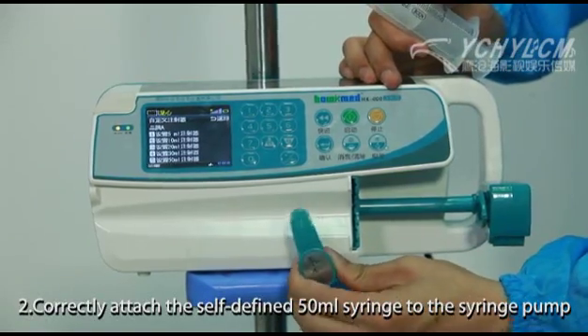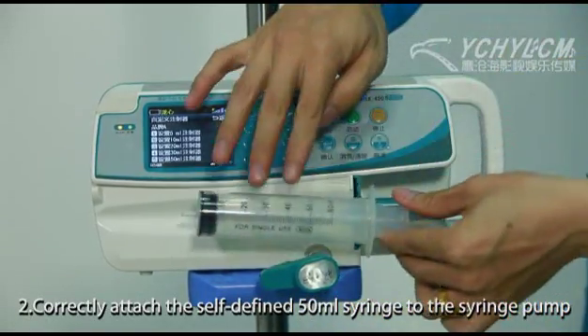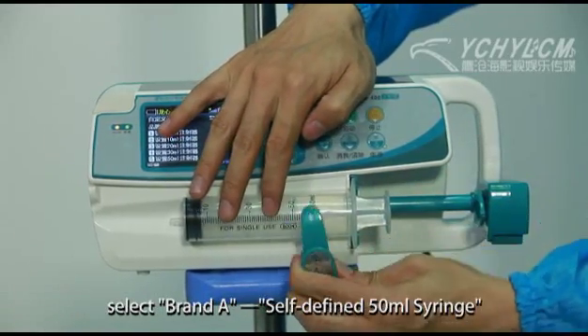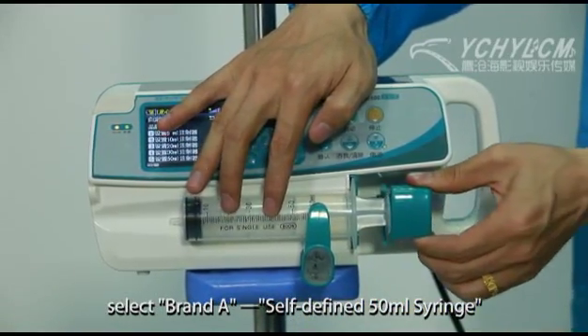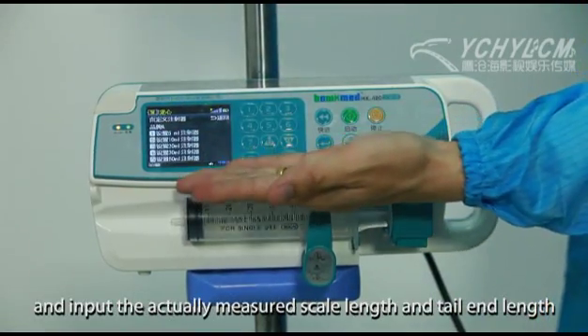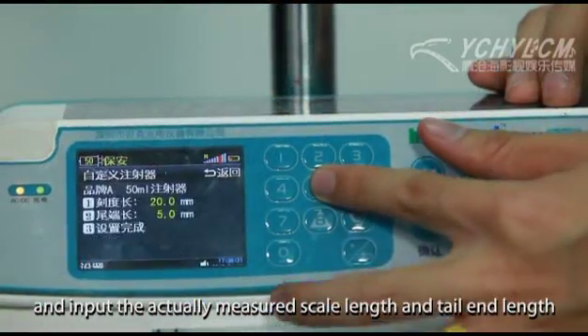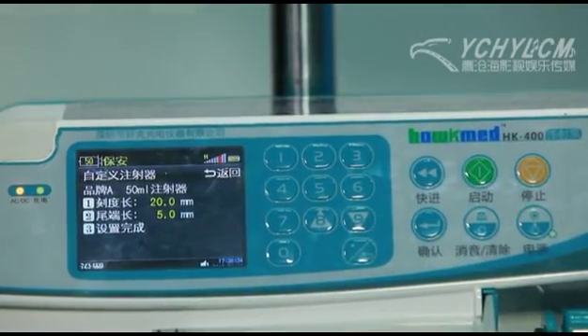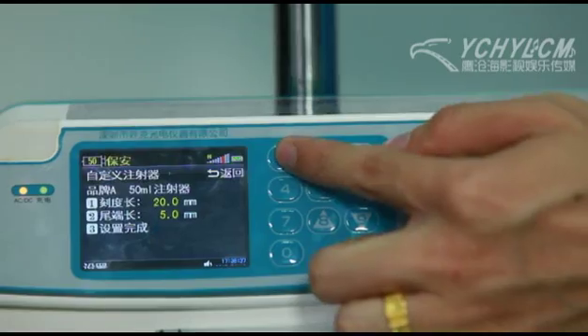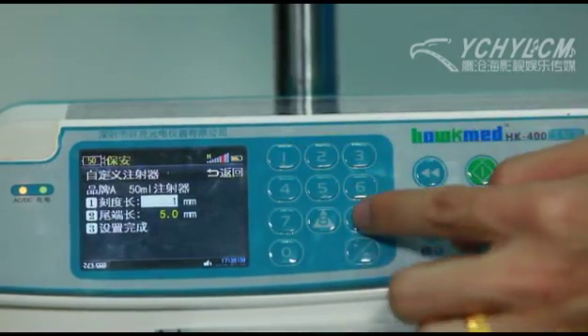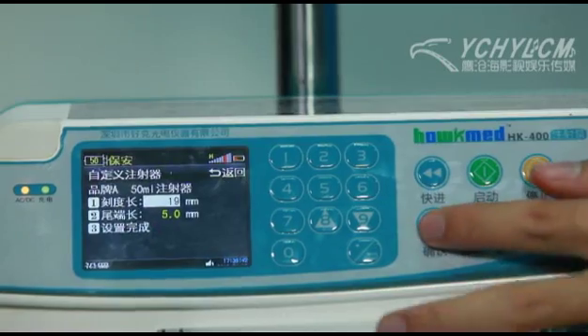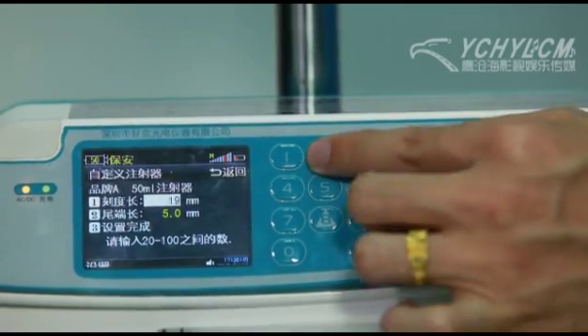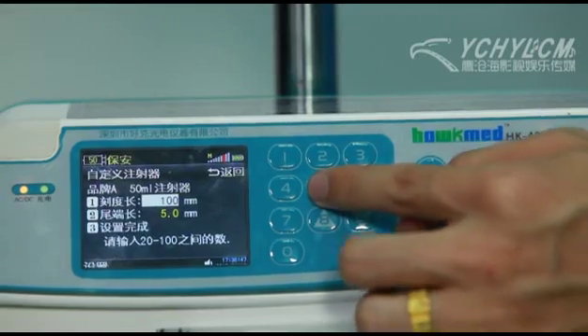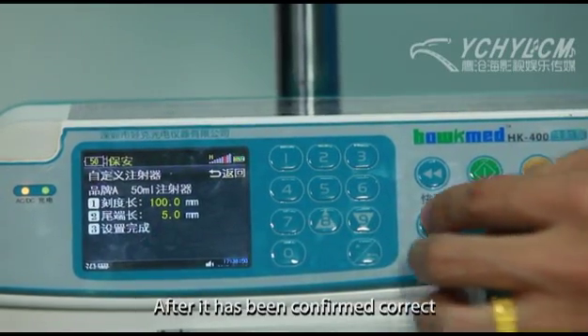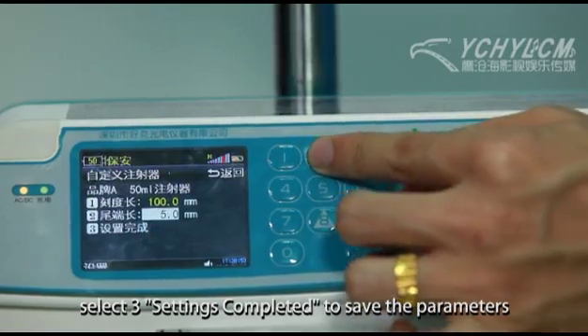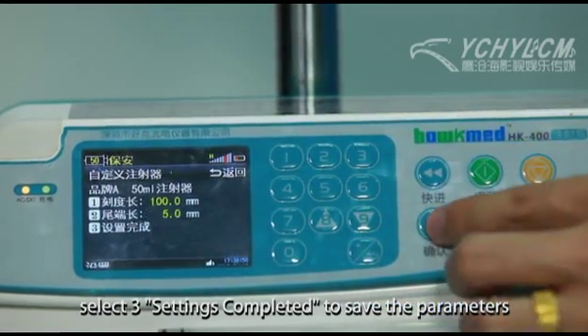2. Correctly attach the self-defined 50 milliliter syringe to the syringe pump. Select brand A, self-defined 50 milliliter syringe, and input the actually measured scale length and tail end length. After it has been confirmed correct, select 3, Settings Completed, to save the parameters.